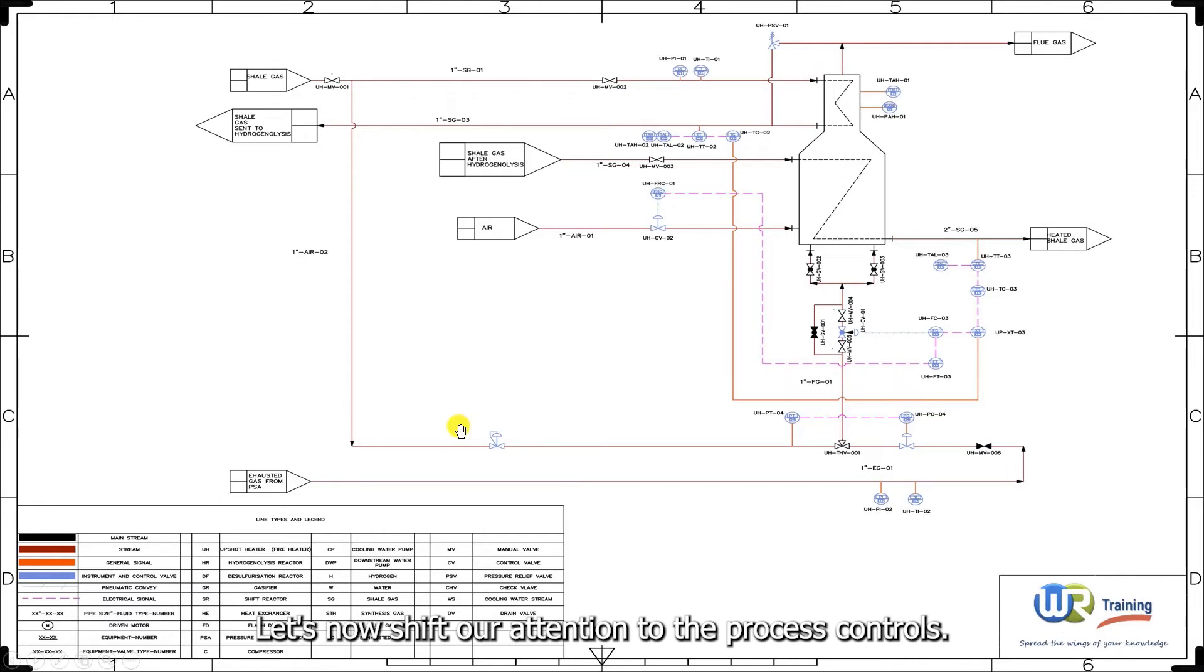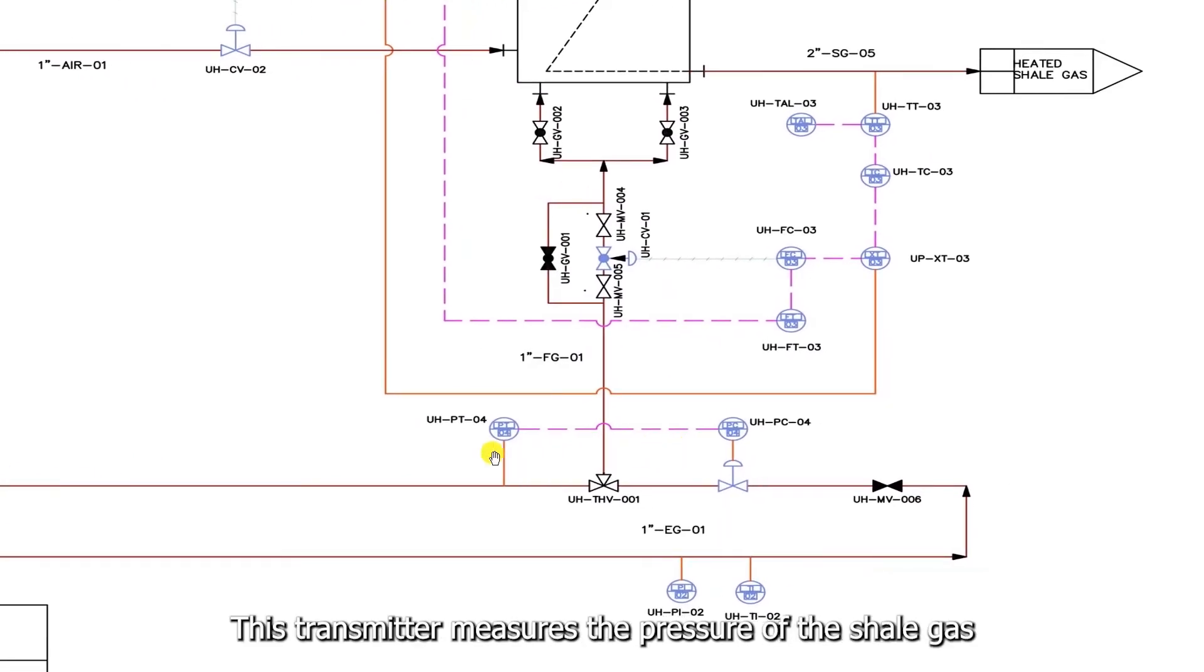Let's now shift our attention to the process controls. This piping and instrumentation diagram includes two control loops. One loop controls the shale gas and the PSA exhaust gas mixture, as seen here. And a second loop controls the flow of the gas mixture to the burners. The first control loop includes a board-mounted pressure transmitter. This transmitter measures the pressure of the shale gas before it is mixed with the PSA exhaust gas.